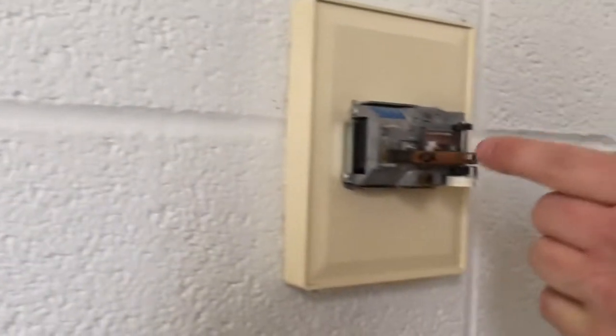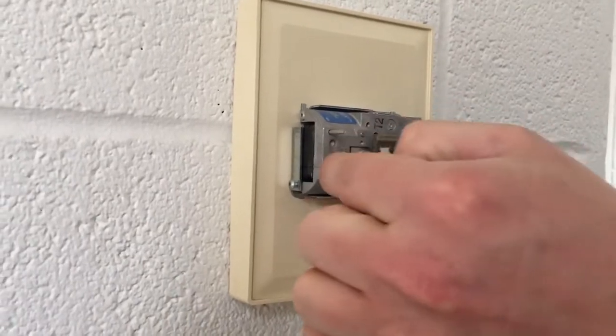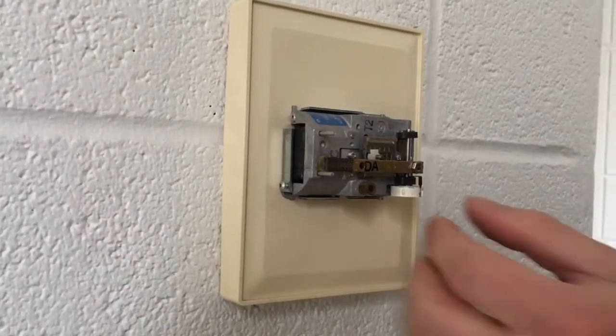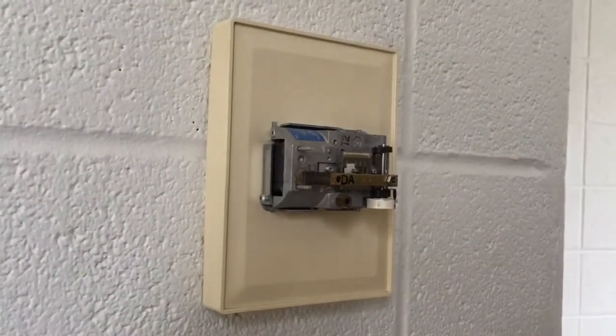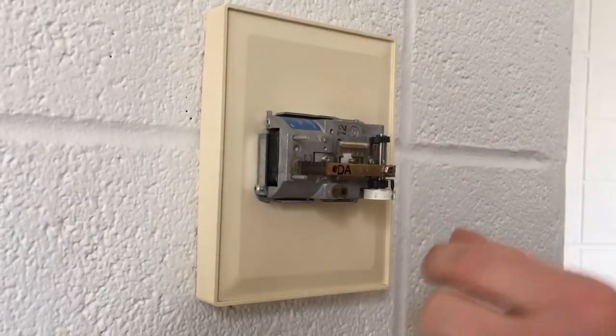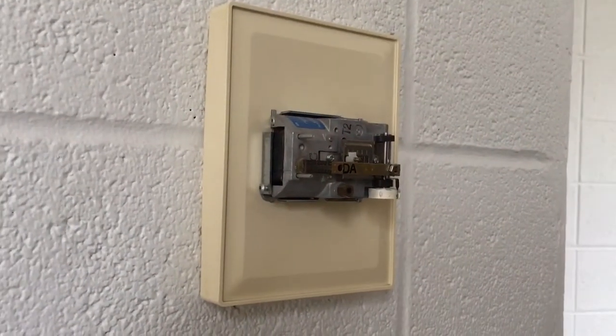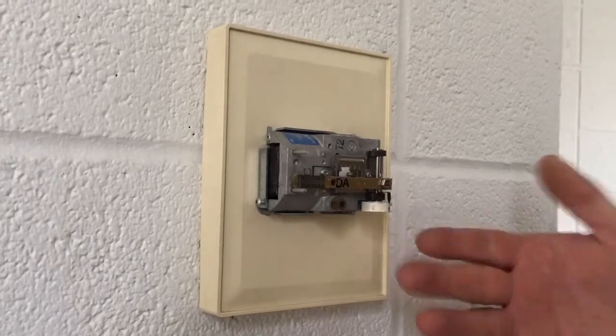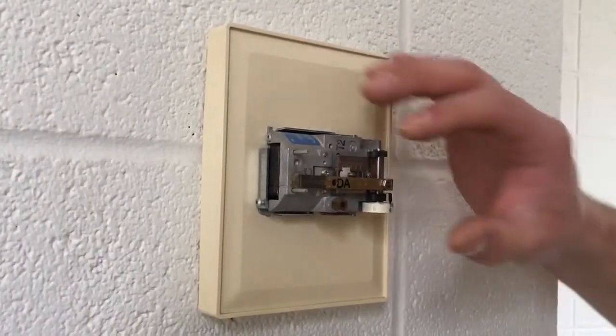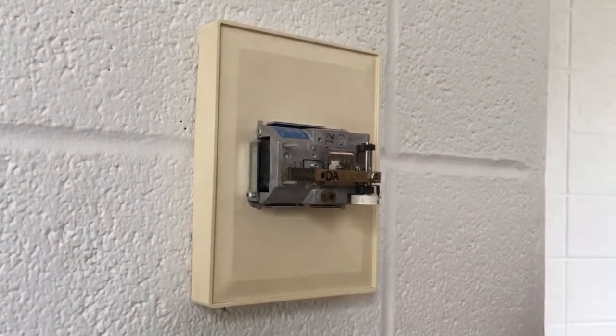To increase the temperature that it thinks the thermostat is, you would want to turn that screw clockwise. It puts more pressure on your bimetallic strip, which keeps it pressed against your vent. If your calibration is too high, then you would turn it counterclockwise to reduce your temperature setting. And then to check it, this strip is very sensitive. Just having my hand here is actually going to change the temperature on it. After you do a calibration, you want to walk away for a couple minutes, come back, spin the dial, and see where your calibration's at.